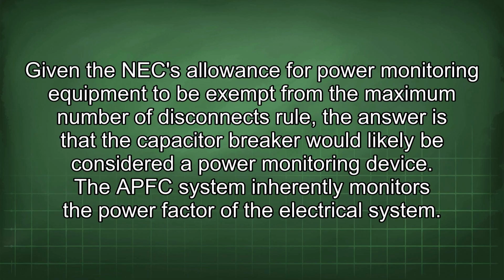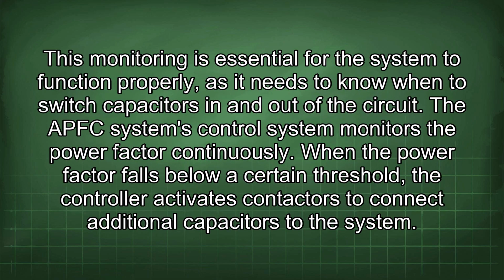Given the NEC allowance for power monitoring equipment to be exempt from the maximum number of disconnects rule, the answer is that the capacitor breaker would likely be considered a power monitoring device. The APFC system inherently monitors the power factor of the electrical system. This monitoring is essential for the system to function properly, as it needs to know when to switch capacitors in and out of the circuit. The APFC system's control system monitors the power factor continuously.